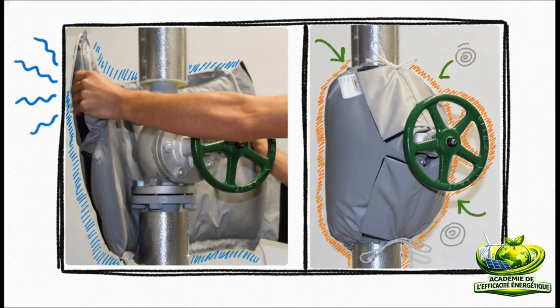Take a look at the bare equipment we have over here. A super common and frankly massive mistake in a lot of facilities is going all out insulating the main process pipes, but then leaving ancillary stuff like valves, flanges, and fittings totally bare. These exposed metal chunks are basically just radiating heat into the room 24/7. But the fix is so incredibly simple. Custom, removable insulation jackets. They just use draw cords and Velcro, which means your maintenance crew can pop them off in seconds without any tools, do their work, and slap them right back on.